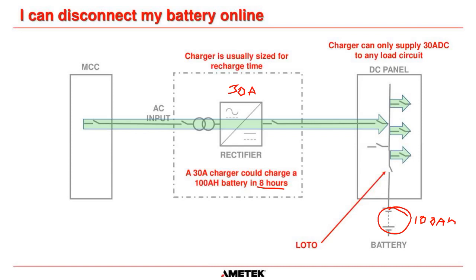That's absolutely fine, because when the battery is called into action, once the power comes back on again, the charger will supply 30 amps to the battery and recharge it, okay? But that doesn't mean that your load circuits are only going to ask for 30 amps, okay? And I'll explain that on the next slide. Because remember, that's all now. The charger can only supply 30 amps.